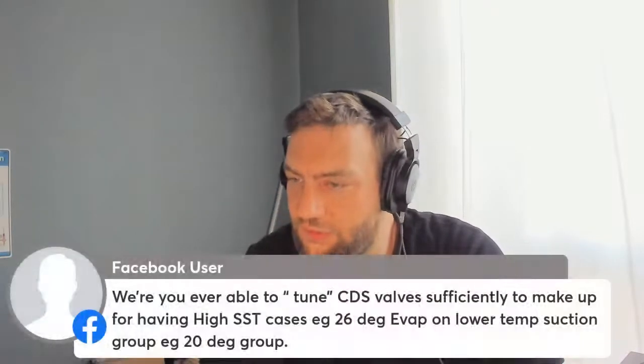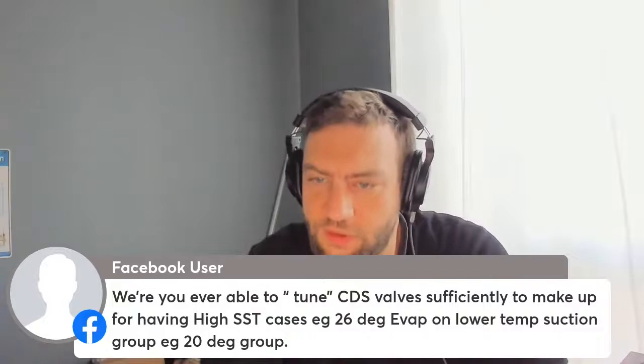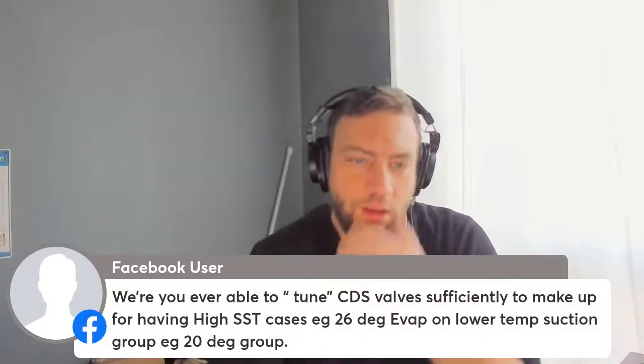Were you ever able to tune a CDS valve sufficiently to make up for having high SST cases? Example, a 26 degree evaporator on a lower temp suction group.